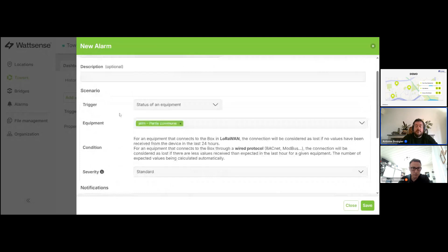You can be advised by email or SMS if you want. Very often this kind of alarm is set for the maintenance people. But if you want to be advised from the value of a property, for example my hourly counter, if this one is outside of a range, I can put the minimum value at 1, so if I lose the information, I will be advised as well. And then I will be informed if my consumption goes above 25 kilowatts per hour.